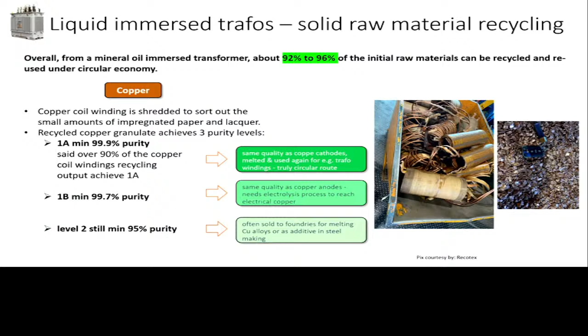We did some studies on transformers that were filled 20 years back, and the best part is there's a fantastic alternate use. Esters can be used to make biodiesel, used in a lot of cosmetic products, and have many industrial applications. Copper is recycled at 99%, while aluminum in oil-filled transformers gets recycled to about 80-85%, because there's more melting loss in aluminum than copper. If you look at carbon content, transformers are not carbon neutral, but they are very close to a circular economy.